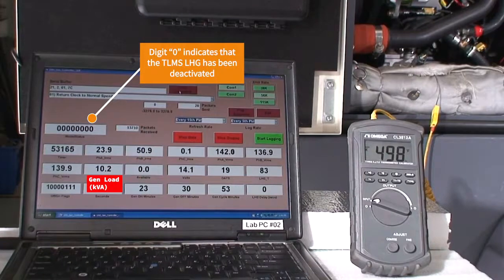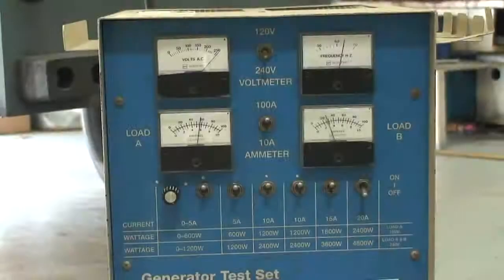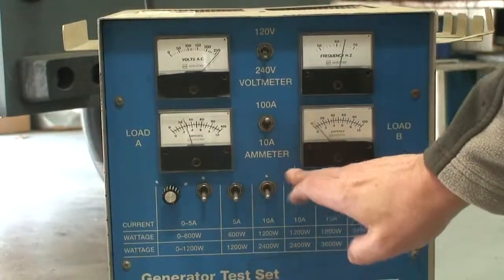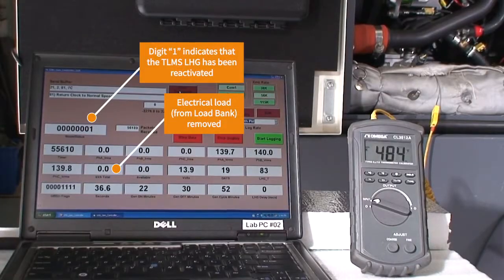We will now turn off the load bank, reducing the electrical load to zero, and the thermal load management system will immediately react by reactivating the LHG. While the load bank was applying 10 kilowatts, the exhaust gas temperature was sitting at about 490 degrees Fahrenheit. Now that we have removed the load bank current and the LHG has been re-engaged, the exhaust gas temperature is sustained at about 490 degrees Fahrenheit.